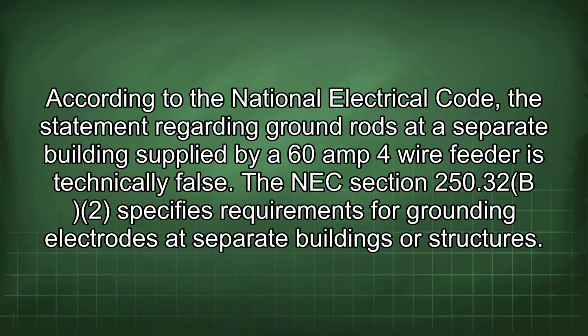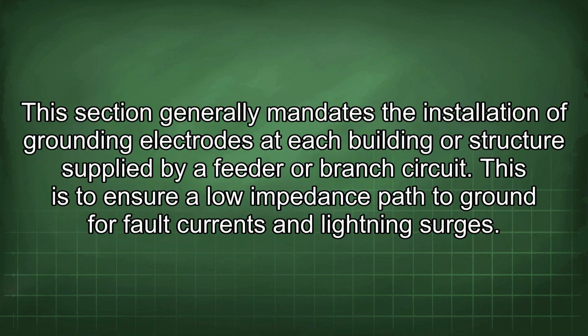According to the National Electrical Code, the statement regarding ground rods at a separate building supplied by a 60-amp 4-wire feeder is technically false. NEC Section 250.32(B)(2) specifies requirements for grounding electrodes at separate buildings or structures. This section generally mandates the installation of grounding electrodes at each building or structure supplied by a feeder or branch circuit. This is to ensure a low impedance path to ground for fault currents and lightning surges.